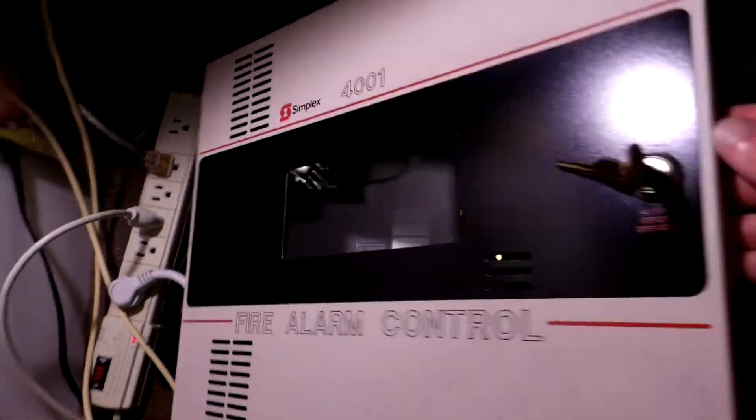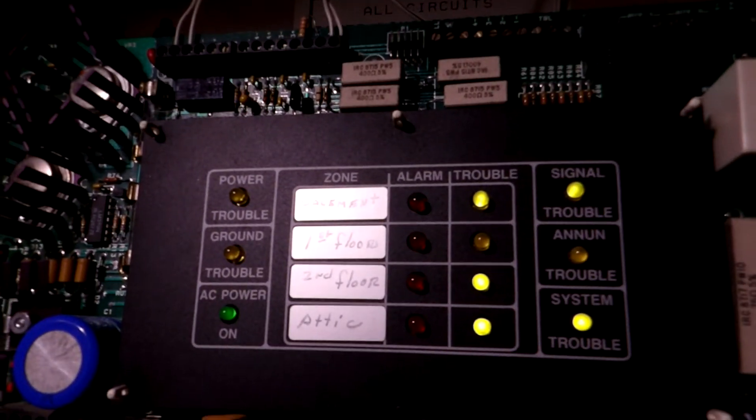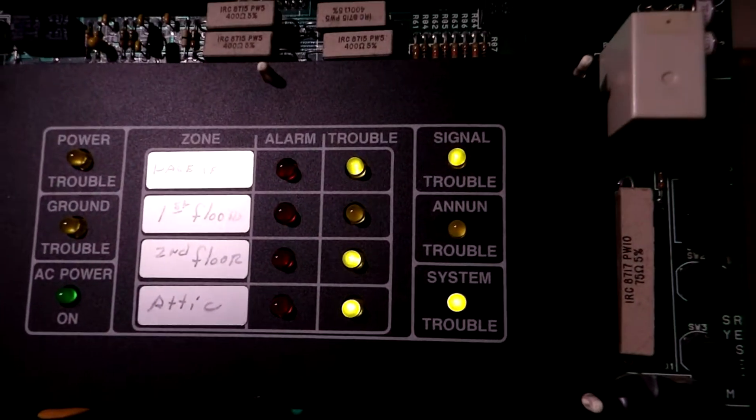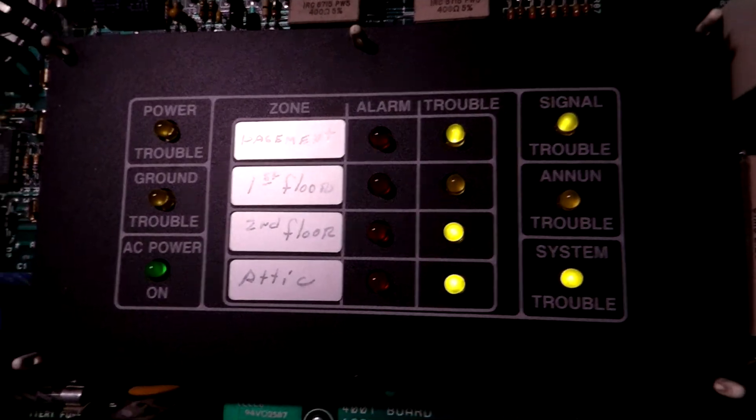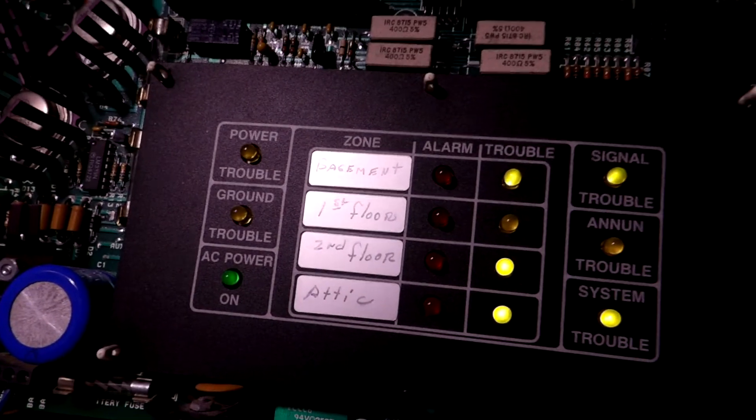We'll open the panel up and just give a quick overview of it. We have troubles on Zones 1, 3, and 4 due to no resistors. Zone 2 has its resistor. And we have a trouble on the signal circuit because, again, no resistor. We also have a battery trouble — we should get a power trouble light because we have no batteries. And the system trouble light is on because the other troubles are active.